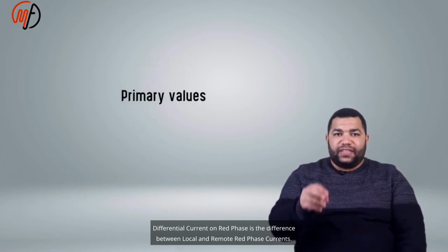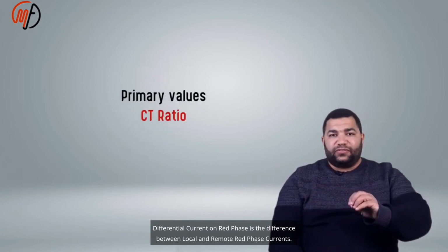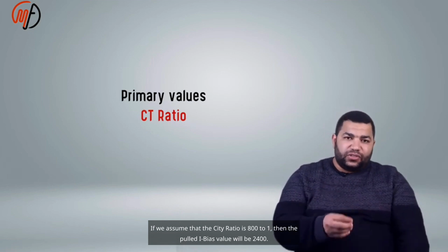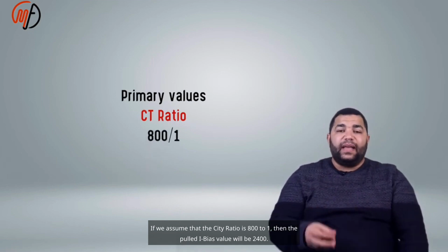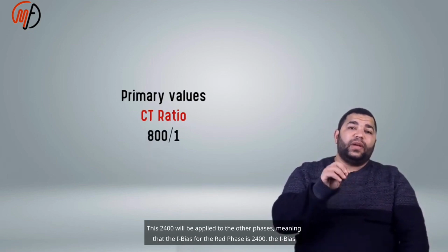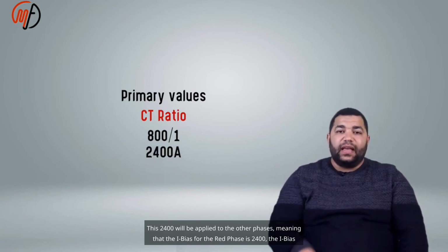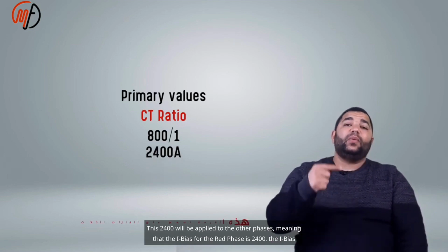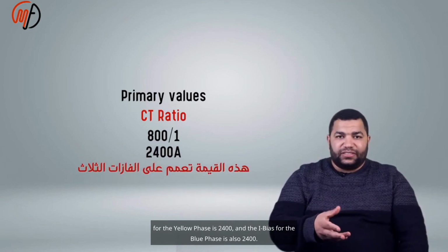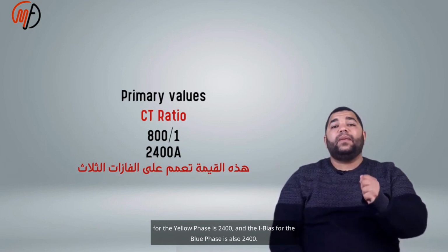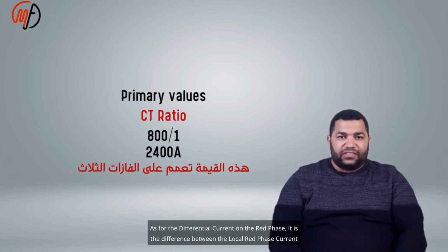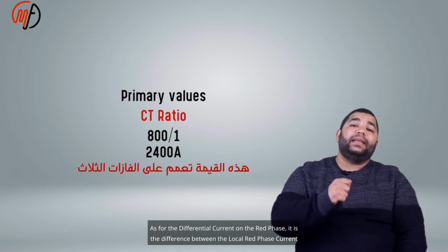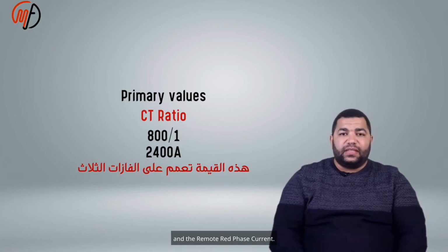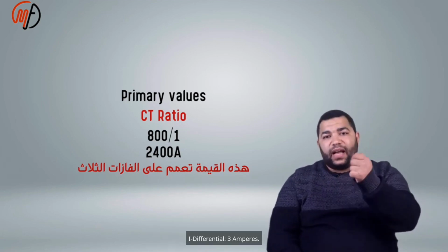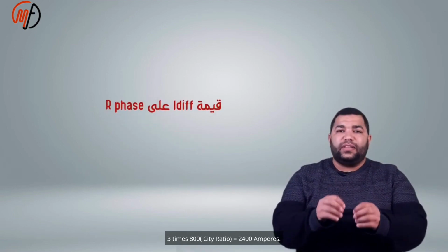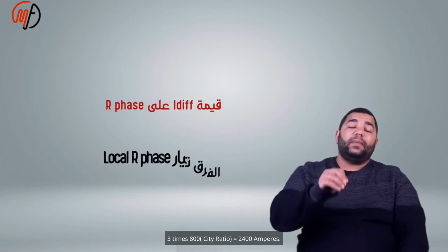Differential current on the red phase is the difference between the local red phase current and the remote red phase current. If we assume that the CT ratio is 800 to 1, then the pulled I bias value will be 2400. This 2400 will be applied to the other phases, meaning that the I bias for the red phase is 2400, for the yellow phase is 2400, and for the blue phase is also 2400. As for I differential, 3 amperes times the 800 CT ratio equals 2400 amperes.